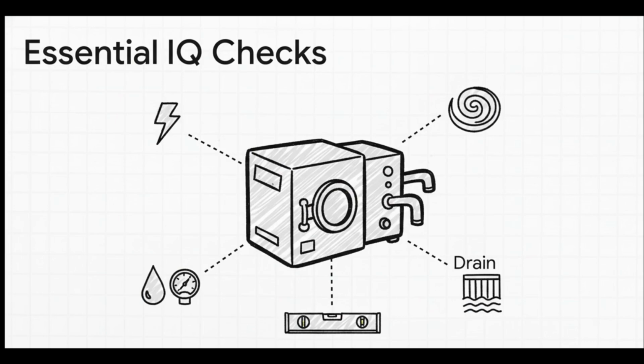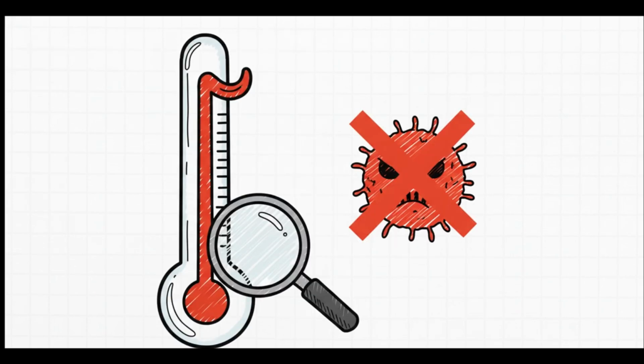And the details they check here are just wild. We're talking about confirming the exact voltage, the exact water pressure, making sure the drain can handle a flood of scalding water, and even getting out a bubble level to make sure the machine is perfectly flat. It's an absolutely exhaustive checklist. But out of all those checks, one of them is, without a doubt, the most important: calibration. Because at the end of the day, an autoclave is really just a fancy, high-pressure hotbox. If its own thermometer is lying, the whole process is a complete failure from the get-go.